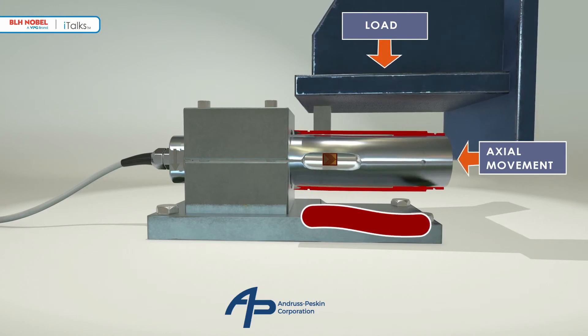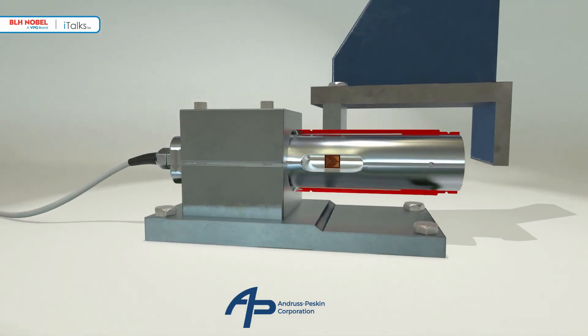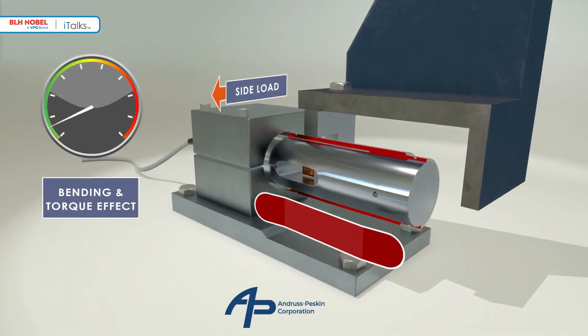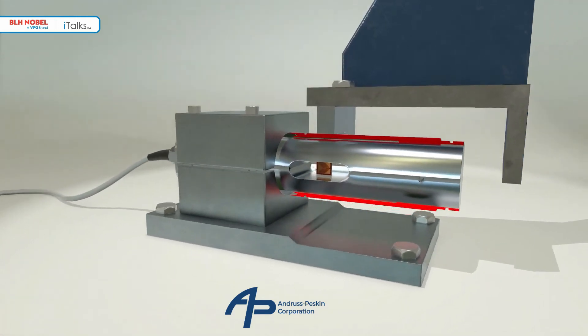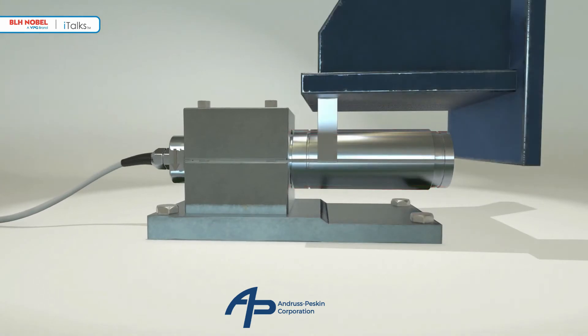The measuring element deforms symmetrically, leaving the strain gauges unaffected by bending moment errors. The beam behaves in a similar way when subjected to side loads, enabling the transducer to reject errors caused by thermal or structural movement. Side loads that arise in the transverse direction due to agitation, wind, or structural deflections are similarly rejected. Even under 100% side load conditions the measuring element maintains its symmetrical form and the weight measurement remains accurate and stable.